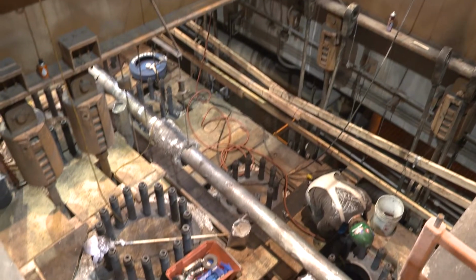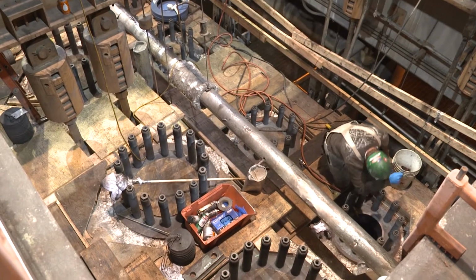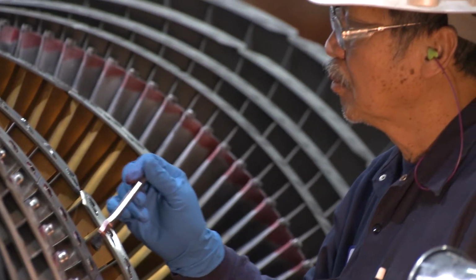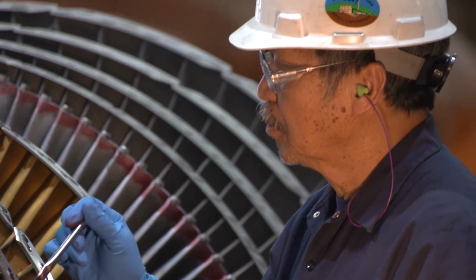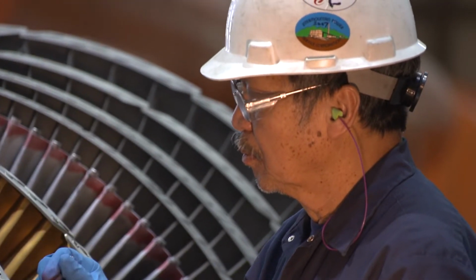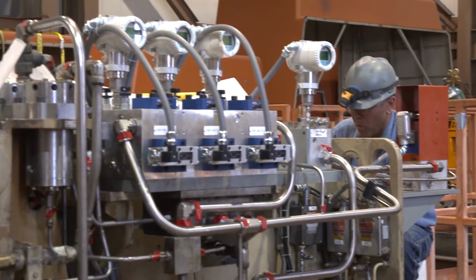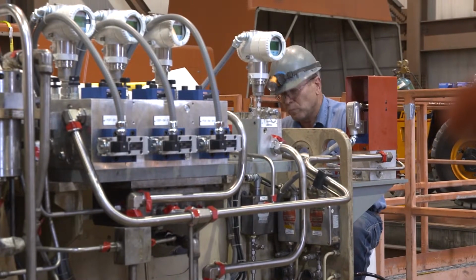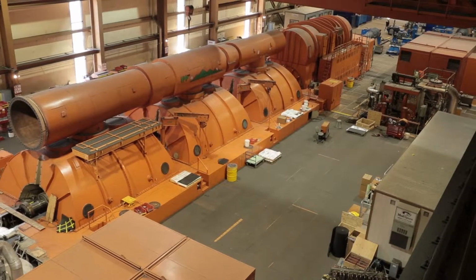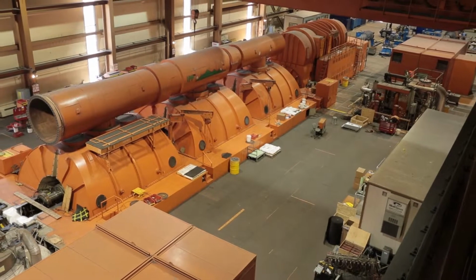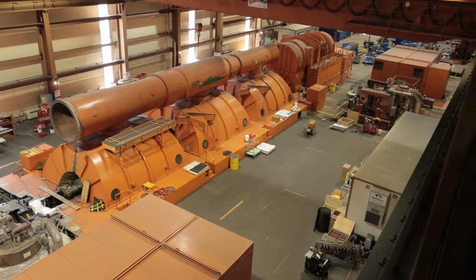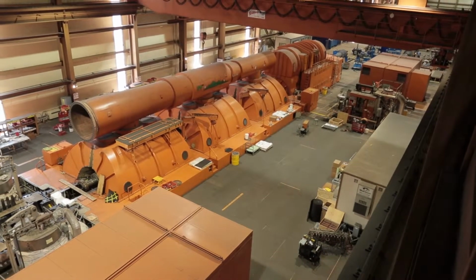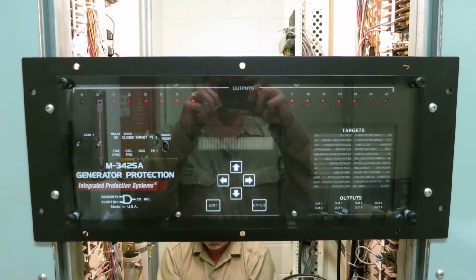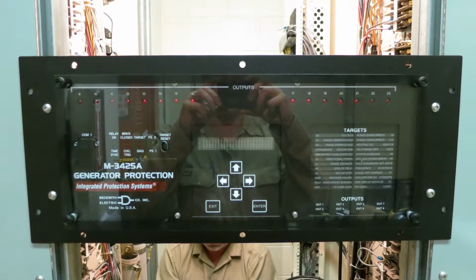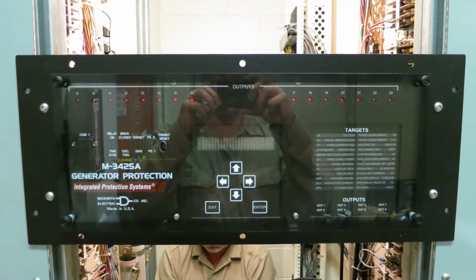Control and stop valves were replaced with a rebuilt set. Turbine lube oil system was filtered and dehydrated due to water contamination issues during shutdown. The mechanical overspeed trip was replaced with an electronic system. Generator had several new temperature sensors and 1 new vibration sensor installed on the T4, T5, and T6 connections. Generator protection relays were upgraded and high pot testing completed.